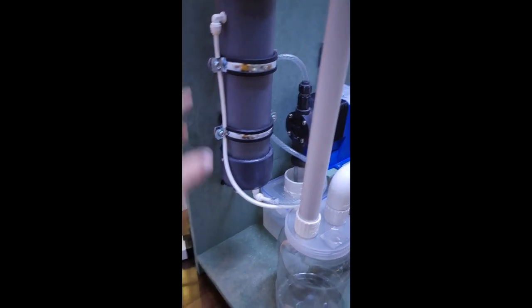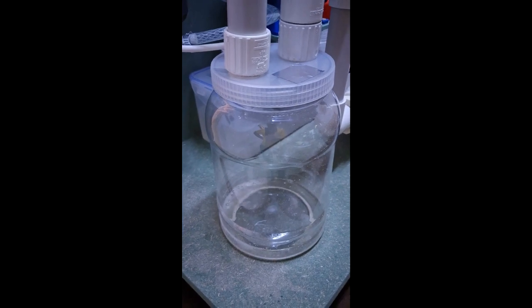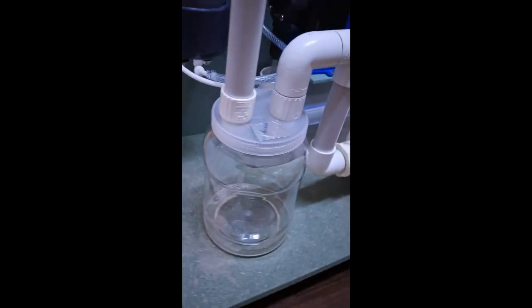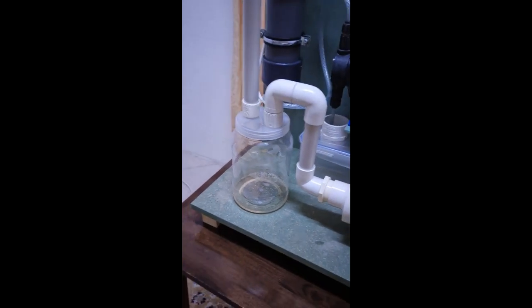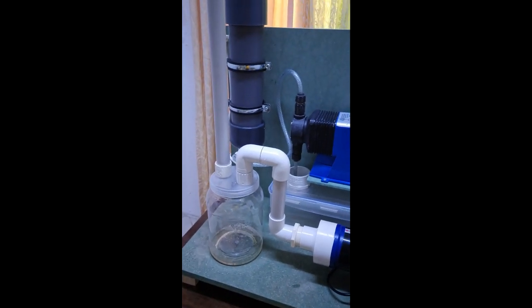And now it started producing the sodium hypochlorite solution, and this is too much flow. We have to reduce it a little bit in the dosing from here in order to reach 60 liters per day. And after a while we'll take a sample and test it for sodium hypochlorite.